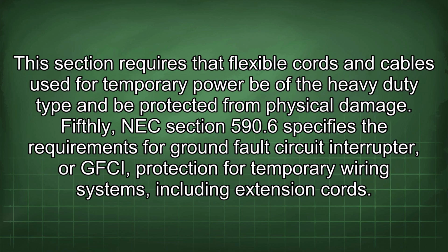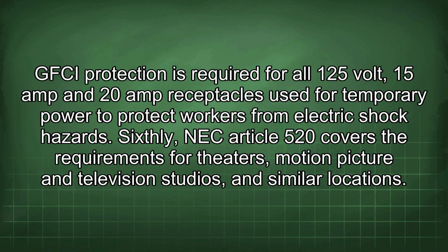Fifthly, NEC Section 590.6 specifies the requirements for ground fault circuit interrupter, or GFCI, protection for temporary wiring systems, including extension cords. GFCI protection is required for all 125-volt, 15-amp and 20-amp receptacles used for temporary power to protect workers from electric shock hazards.